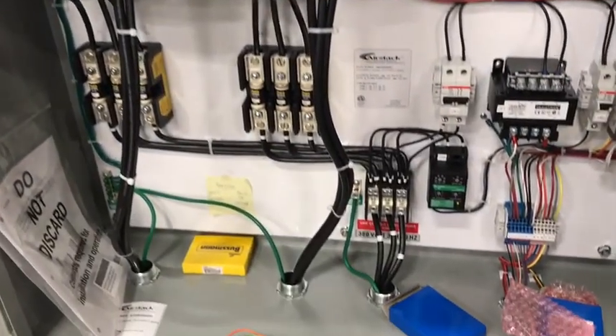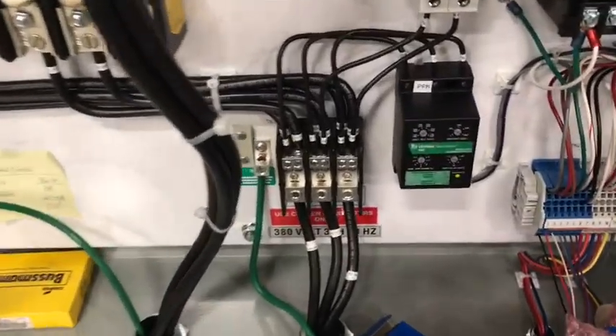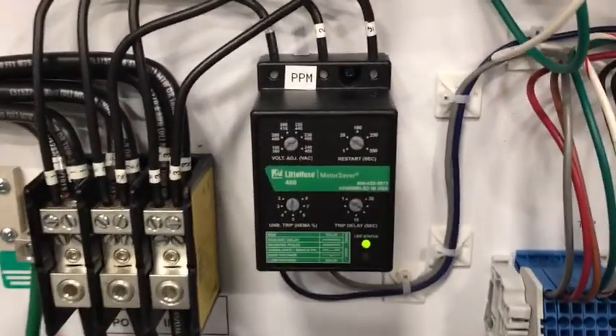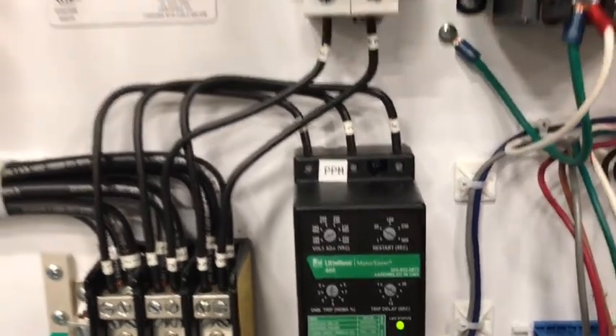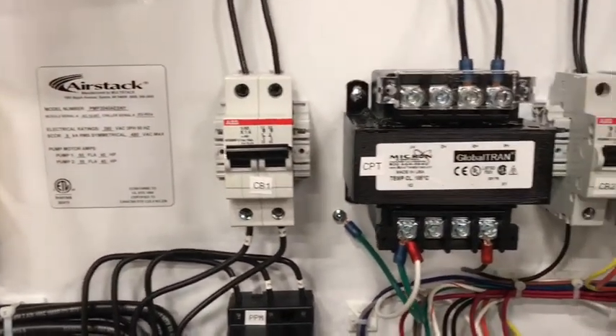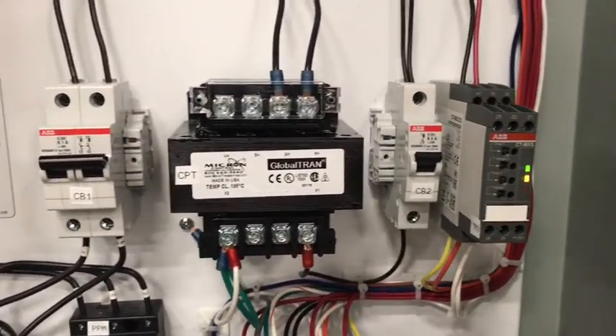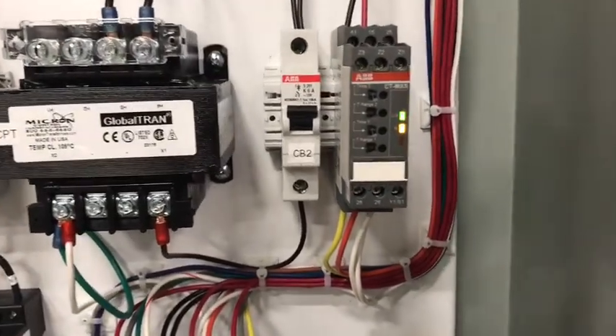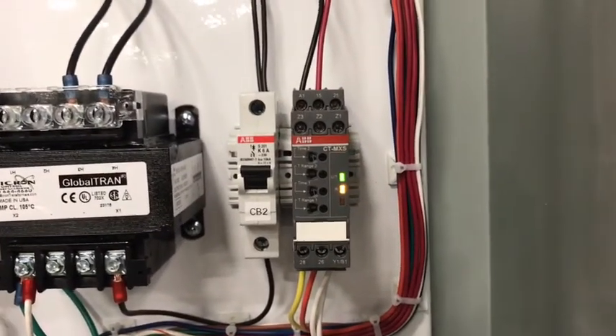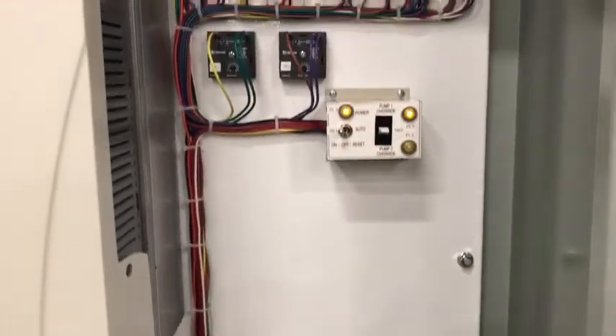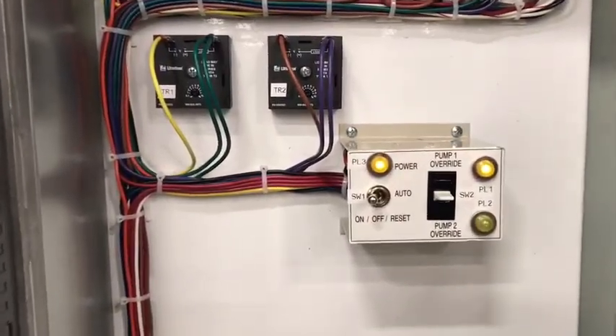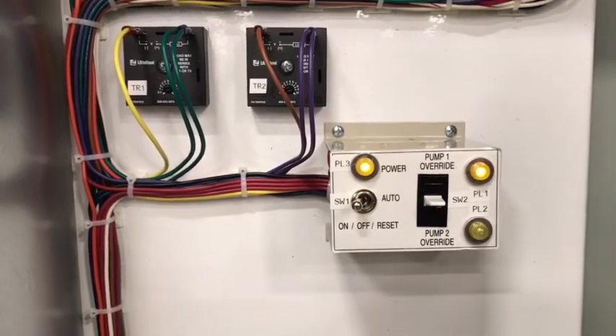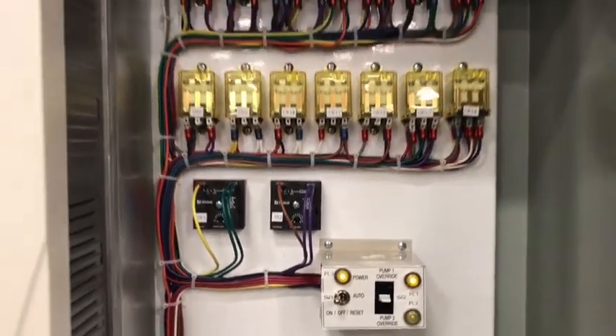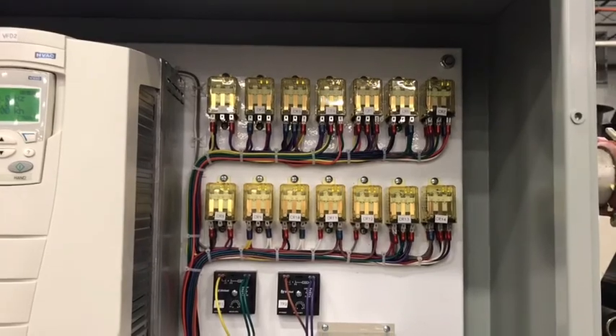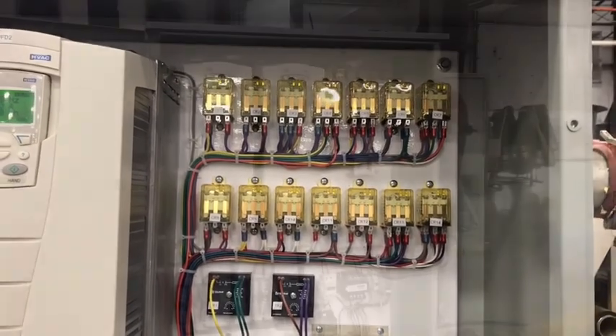And then as we come back down, we'll see the power phase monitor just to the right here with the settings adjustable for over voltage, under voltage, etc. Control power transformer there, the black device in the middle, control power breaker, and then an automatic timer, that ABB device for switching pumps. We have our two timers there, TR1 and TR2, that are tied to our flow switches, and then relays for the basic pump cabinet control logic.